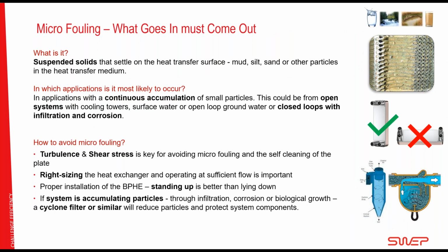That was it. Microfouling. Here will be a little bit more, stay a little bit longer. So what is microfouling? It's suspended small solids that settle inside the heat transfer surface. Where do we see it the most? Well, where there is continuous accumulation of small particles. What do I mean by that? Well, where there is an addition of dirt over the lifetime of the system.